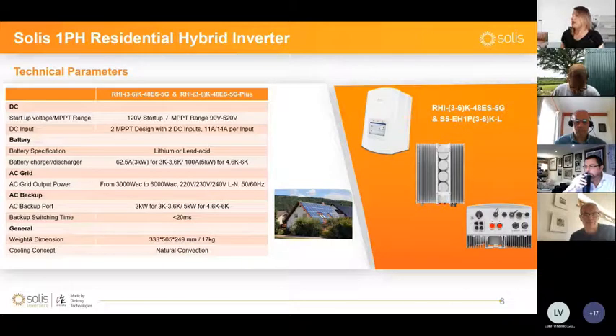Additionally, the battery compatibility list includes a lot of lithium batteries, but they are also compatible with lead acid batteries. For the system to work properly, they're going to need additional temperature sensors that we can help provide, because lead acid batteries do not communicate over CAN with the inverters. So if you ever have such a system, if you're working on installing such a system, get in touch with us, and we can help you provide that to the customer and to the installation.